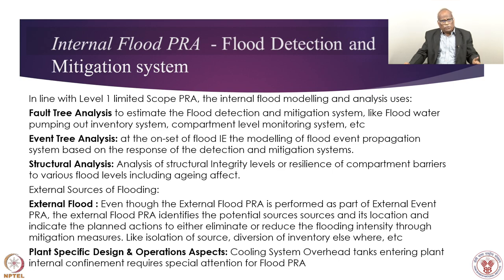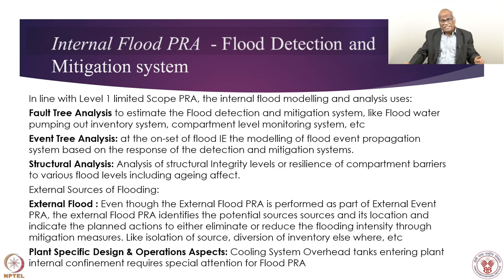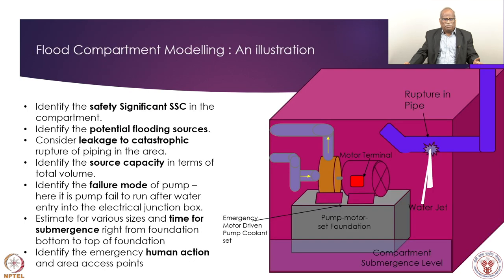Unless external flooding manifests into internal flooding, the plant generally remains in a safe state after shutdown. Plant-specific design aspects must also be addressed. We may have a generic flood list, but we must generate our own list considering plant configuration — different compartments, routing in terms of drain points leading from one area to another, capacity of drains, and the worst-case rate at which water can enter the plant.